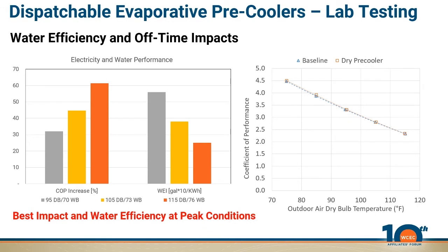Another question you could ask is, if I put this device on my air conditioner and I'm not using it most of the time, is it causing a problem? Is it going to reduce my efficiency because I've got this device sitting on my air conditioner? The short answer: here's the coefficient of performance as a function of outside temperature for a baseline versus a dry pre-cooler. At least for this particular product, there was no discernible negative impact when it wasn't operating.